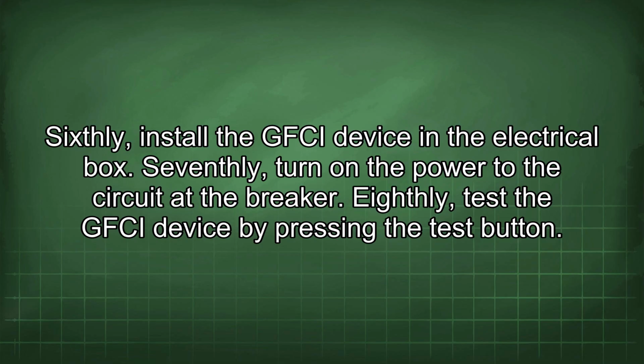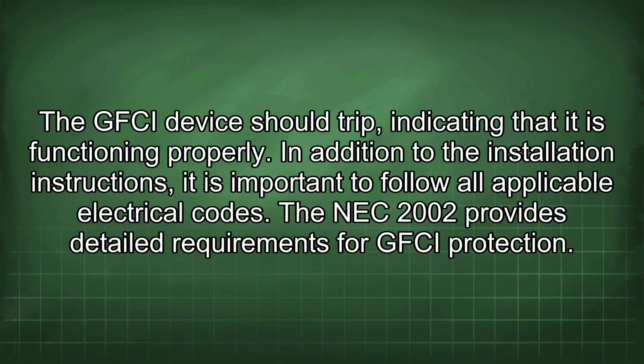Sixthly, install the GFCI device in the electrical box. Seventhly, turn on the power to the circuit at the breaker. Eighthly, test the GFCI device by pressing the test button. The GFCI device should trip, indicating that it is functioning properly.